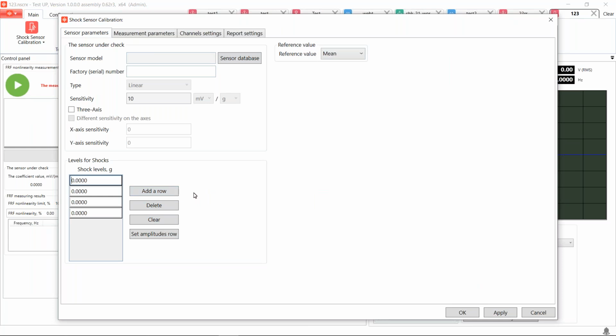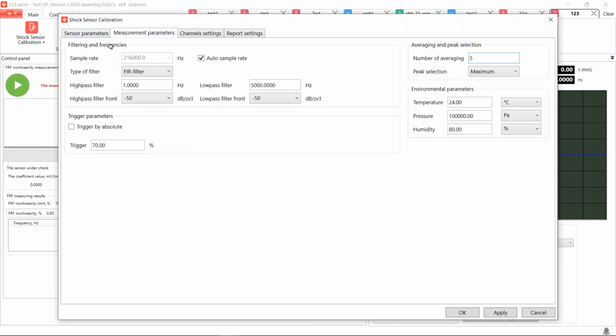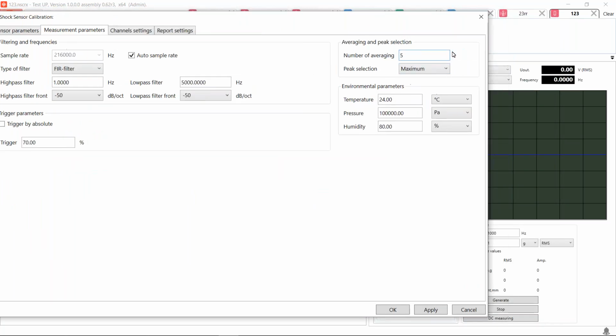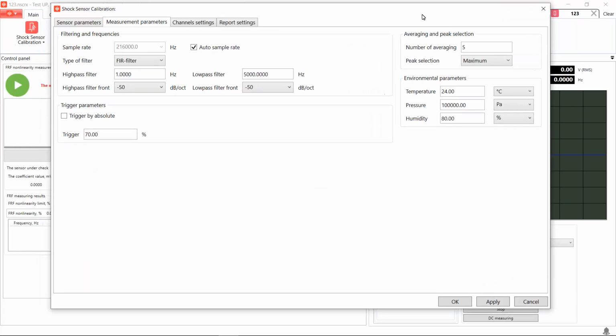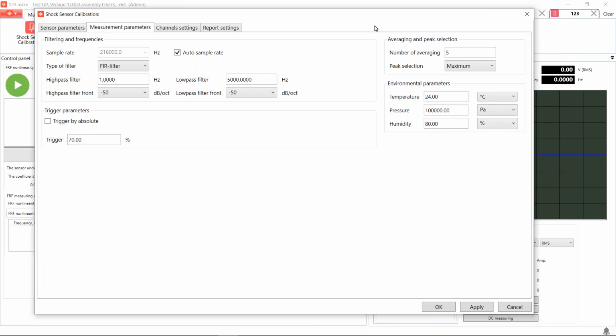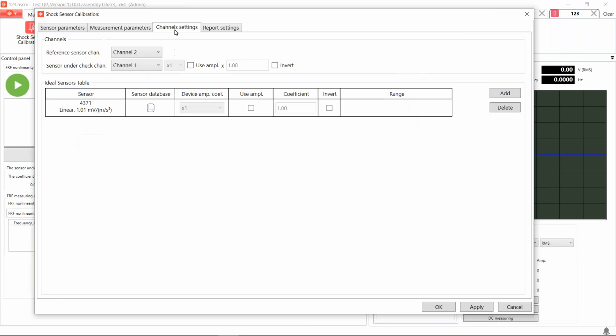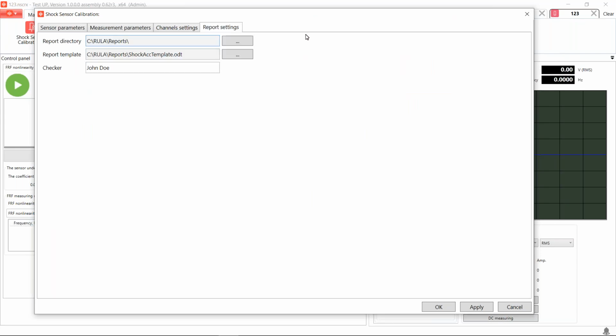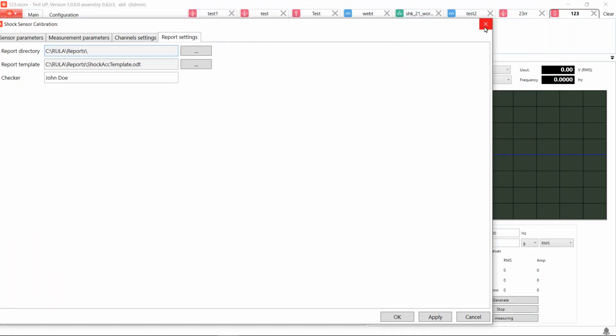Next, you need to add measurement parameters and the number of averaging, which indicates the number of shocks you need to apply for each level. And the number of averaging can be found in the measurement parameters tab. So it is here on the right side. So for example, we put here 5 shocks we need to do. And in the channel settings tab, you need also to add reference accelerometer parameters and define the channels for the reference sensor and the sensor under check. And as it was for the sensor calibration, you also need to fill in the report settings, and after the calibration procedure, you will get the report.